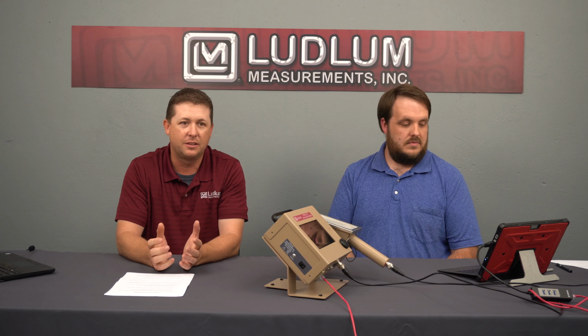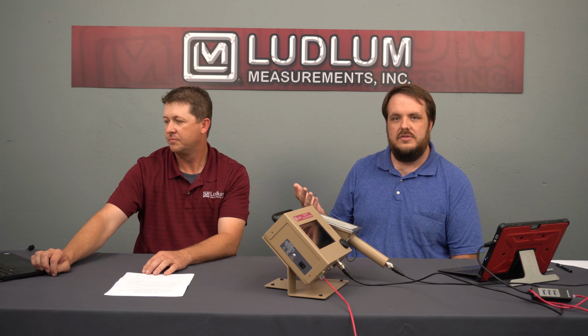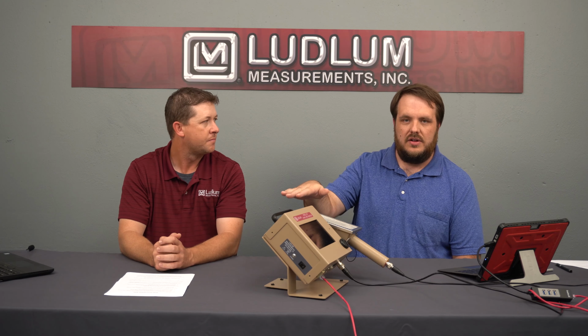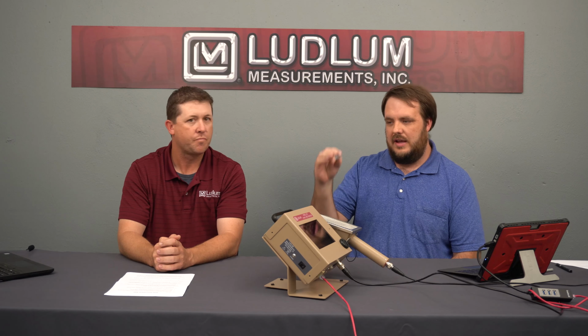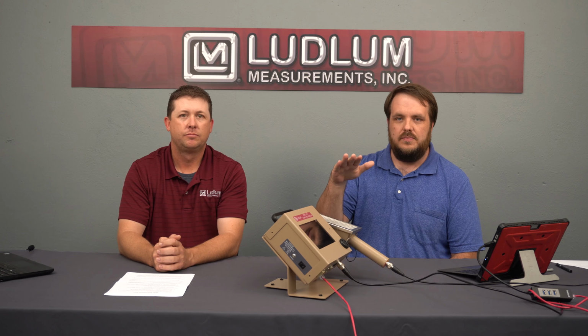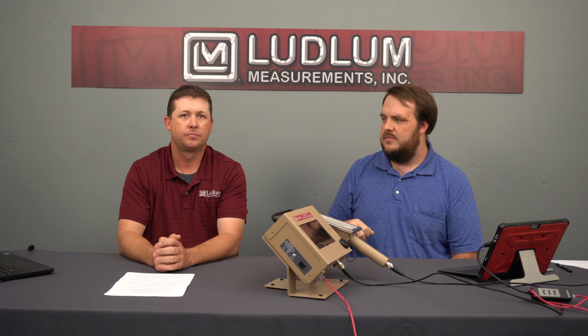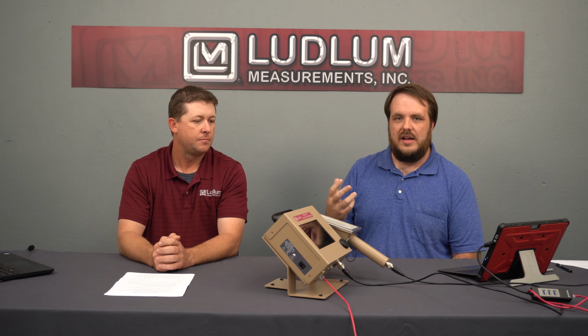Oh, one more question. I'd like to know more about the hand monitoring portion, any sensor? Well, again, there's not one on this unit. The hand-foot monitor has 2 IR sensors. You would put your hand on the detector, and just above it there's an IR beam break sensor that you have to break, and that's how it activates that sensor. If that's what you meant.